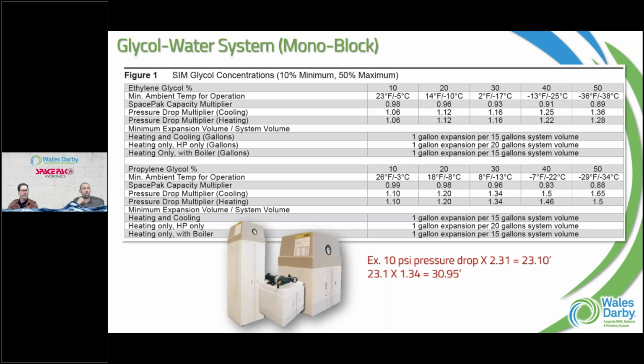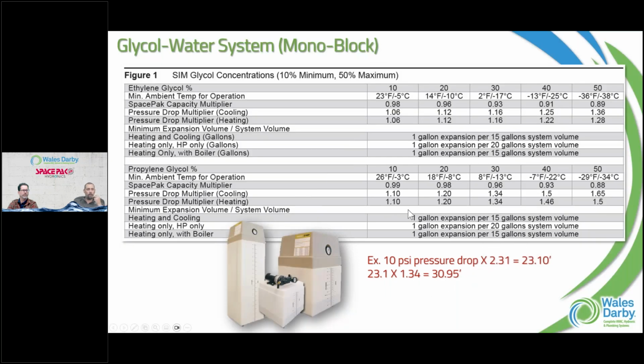And then we come to this chart, and you can see the top is ethylene glycol and the lower one is propylene glycol. If we were doing 10%, we look at a pressure drop increase. So whatever that pressure drop we calculated was, multiply that by 1.10, and that's going to be your final number for 10%. As we go up, you can see that number gets larger. And on the other side of that is the capacity. So at 30%, you would multiply by 1.34.